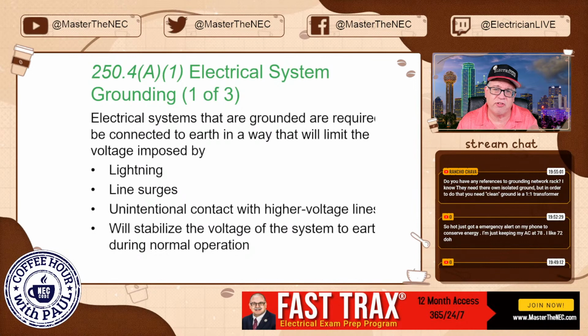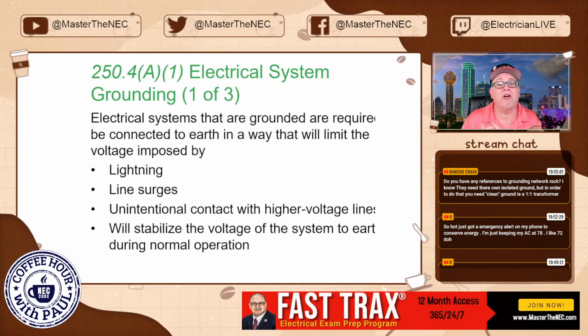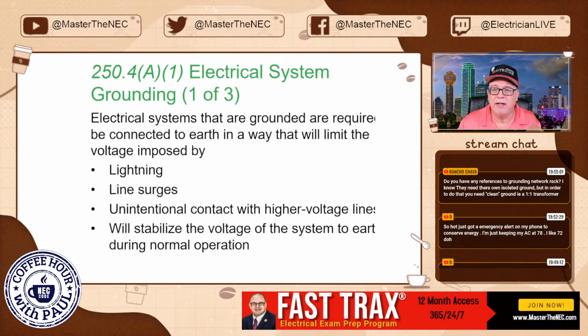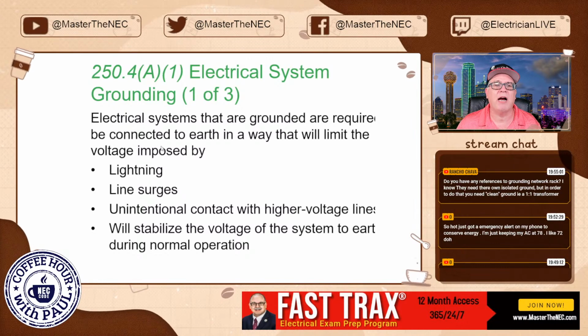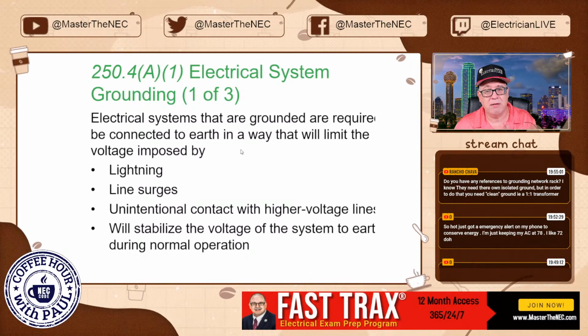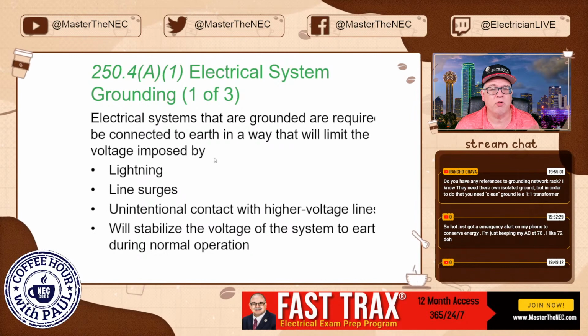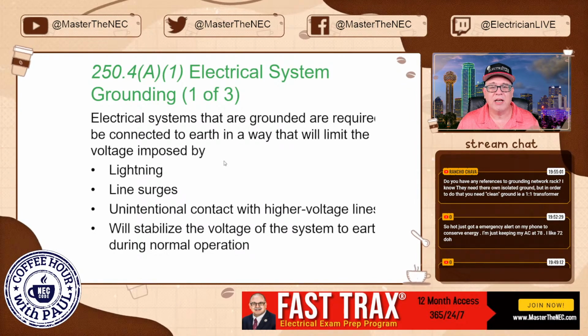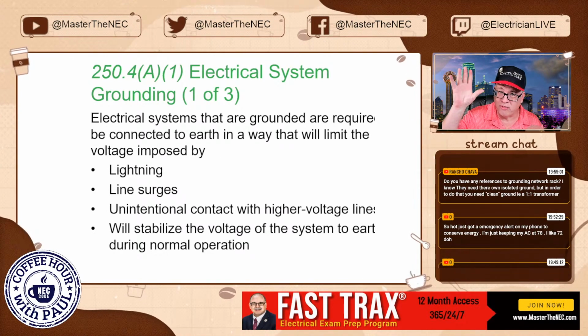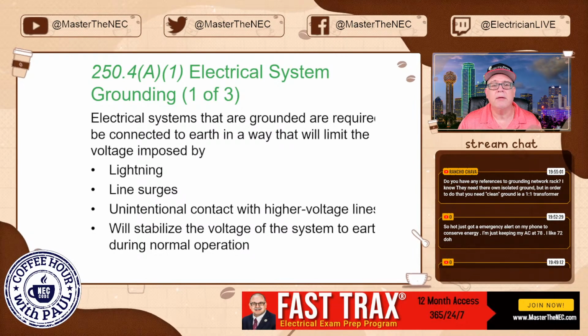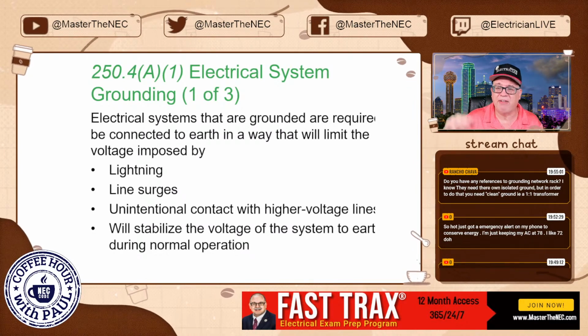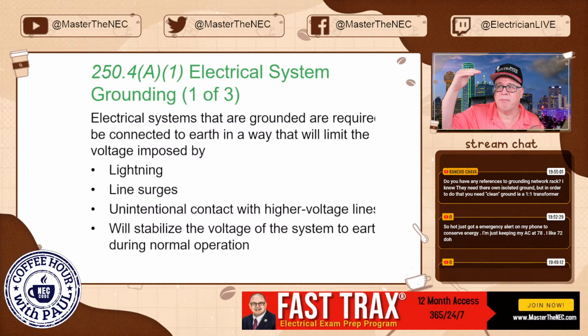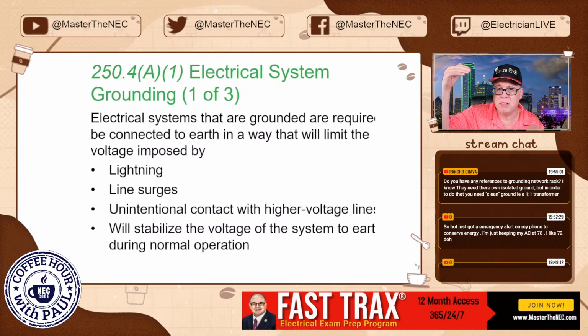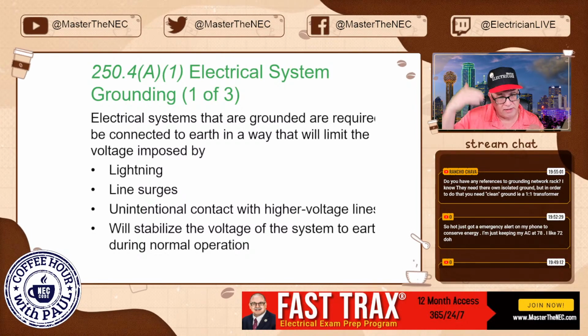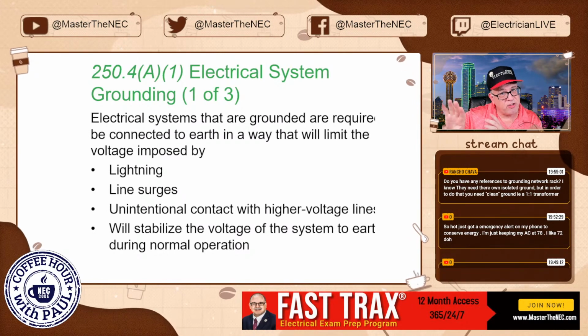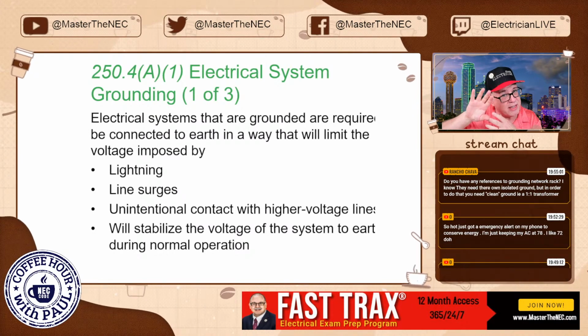If it's established that we have electrical systems that are grounded or required to be grounded, then they are required to be connected to earth in a way that will limit the voltage imposed by, as you saw me read earlier, lightning. Lightning strikes the system, it's trying to get to earth. Line surges: you might have a surge upstream on the high power lines. It's trying to stay in their system. It doesn't need to come into our system.